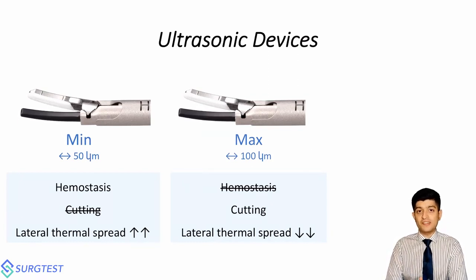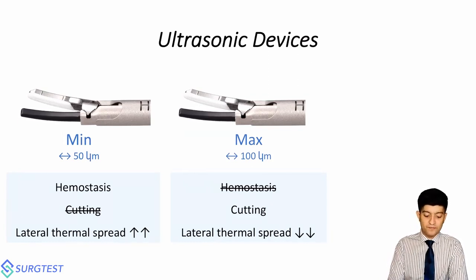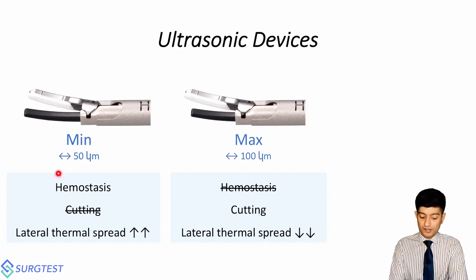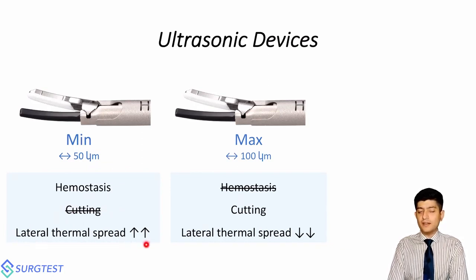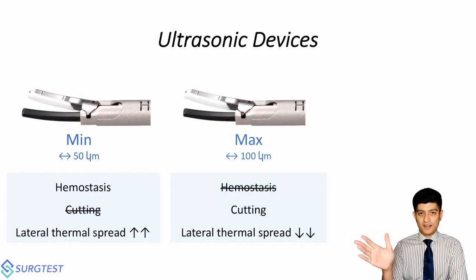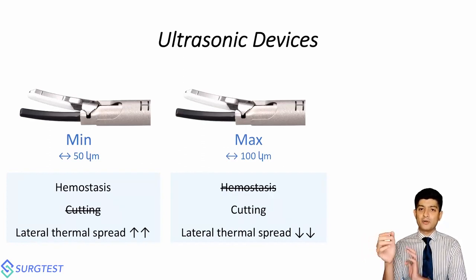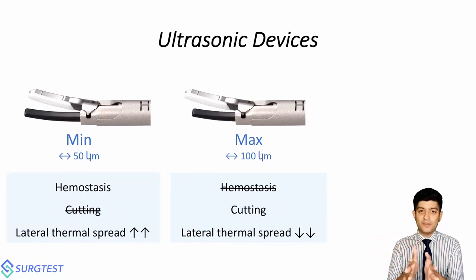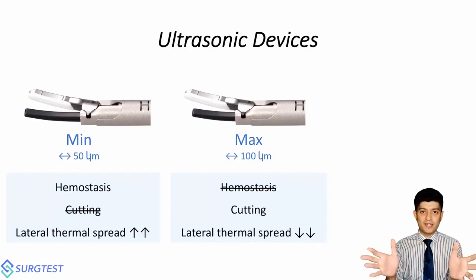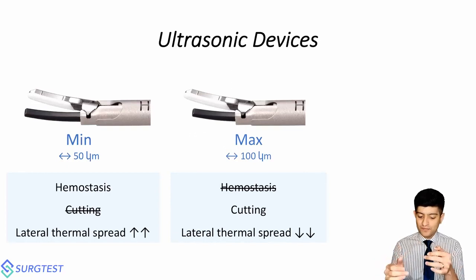Instead, what gets changed is the amplitude of the oscillation which is occurring. When you're using the minimum setting, usually it's a 50 micron to-and-fro oscillation that produces extremely good hemostasis, does not have a cutting effect, but the amount of lateral thermal spread ends up increasing. Now, this is similar to what happens even in monopolar energy devices, right? If you don't stretch the tissues enough, don't reduce the resistance enough, energy gets dissipated to the surrounding tissues and you'll end up having lateral thermal injury.